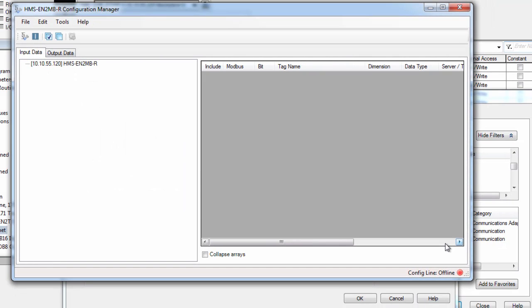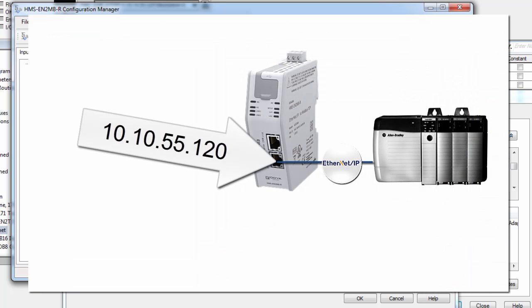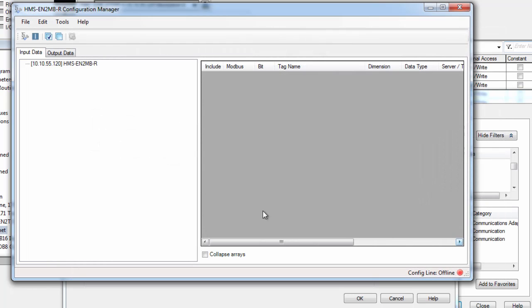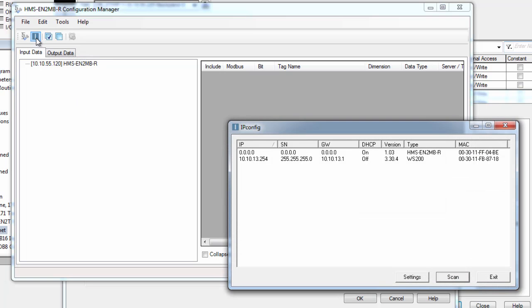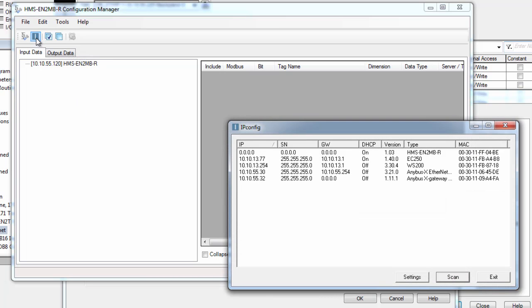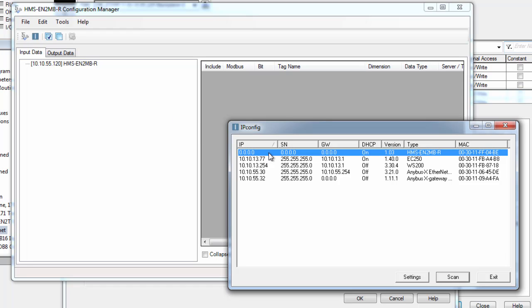First I need to set up the IP address for the linking device in the Configuration Manager as well. As you remember this was 10.10.55.120. Now I could have done this externally using bootp before configuring the linking device, but I can also use the included ipconfig tool which is included in the package from HMS. So I can see that our module has been detected by ipconfig and I double click to configure the IP address.